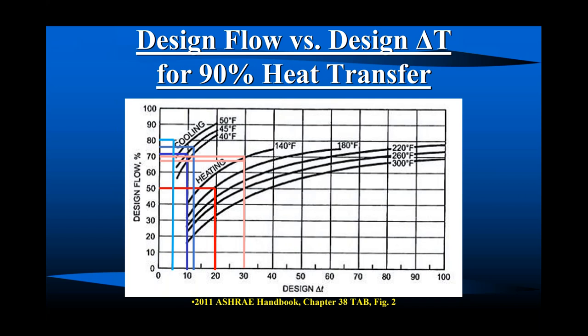That system is probably going to be in play a lot moving forward with what we know now and the need for ventilation and to be able to work with cool water and warm water. So a lot of bad stories out there regarding sensible cooling, even some condensing boiler problems that we're aware of. So a quick question, what happens if the flow to the chilled beam is insufficient, right? Chilled beam, sensible only cooling. What have we seen happen out there? Well, the zone in which that chilled beam, or a number of chilled beams, doesn't cool, doesn't perform. How is this fixed?